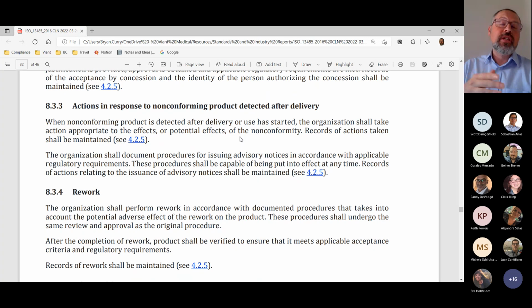But in the case of the FDA specifically, and in almost all cases from a geographical standpoint, if you're going to do a recall, you can't just send a recall notification to all the hospitals and doctors' offices and ask them to send you back the product. You also have to notify the FDA specifically that you are issuing a recall or some kind of field advisory.